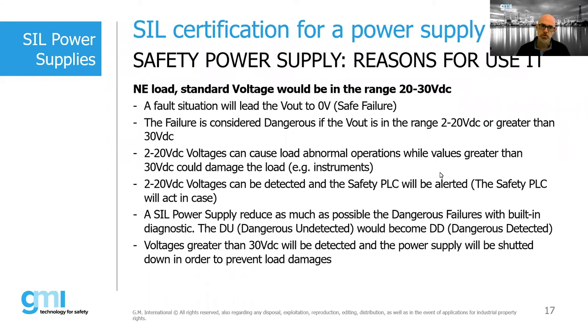As regards energize to safe applications, typically normally de-energized loads, as mentioned above, redundancy is essential to reach a SIL2 or SIL3 level. In fact, without redundancy, with a single safety power supply, only SIL1 level can be reached, and also availability to the process is low. But by composing a configuration 1 out of 2 or 1 out of 3, it's possible to get a higher SIL level up to SIL3 and at the same time increase the availability of the process also for energize to safe applications.